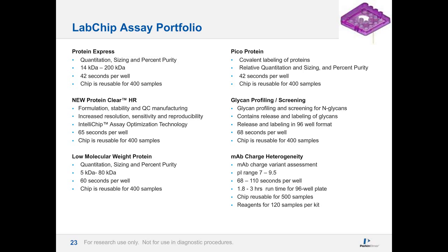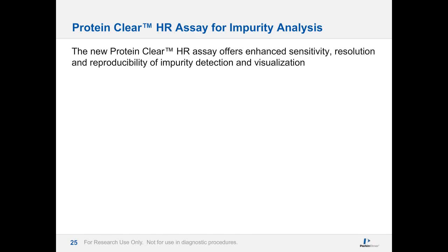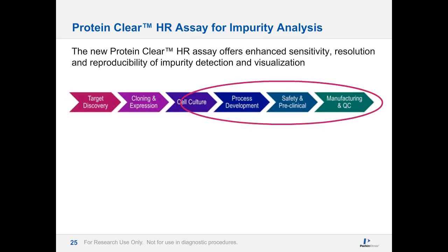The PICO Protein is the covalent labeling assay, where we label proteins prior to loading and separating on the chip. Its main advantage is the highest sensitivity — if you need even higher sensitivity than Protein Express and Protein Clear, PICO Protein rivals silver staining sensitivity. The Protein Clear is quite sensitive, going down to 5 nanograms per microliter with LIF detection. We also have glycan profiling and screening for N-glycans, and our charge heterogeneity assay that works with a pI range from 7 to 9.5 to study the charge of your proteins.